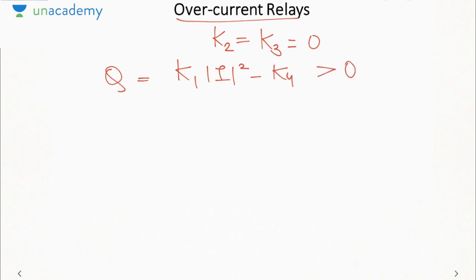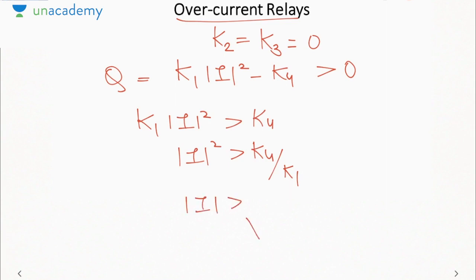Now this must be greater than 0 for relay operation. That means K1 mod I square must be greater than K4, or mod I square must be greater than K4 by K1, or we can say mod I is greater than under root K4 by K1. This will be called as your pickup current. So as we see, the condition that is coming is that the current through the relay must be greater than pickup current for its operation. This is the basic condition for the overcurrent type of protection. Hence, we can design overcurrent relays, or we can determine the performance of overcurrent relay on the basis of universal relay torque equation. Okay.